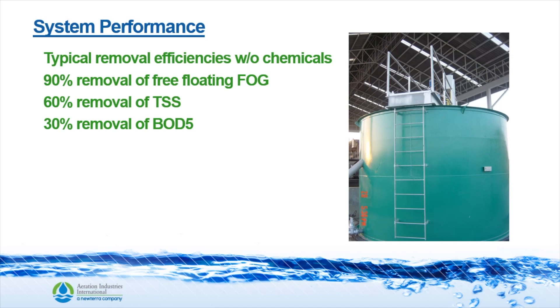Typical removal efficiencies without chemicals are as follows: 90% removal of FOG, 60% removal of TSS, and 30% removal of BOD.